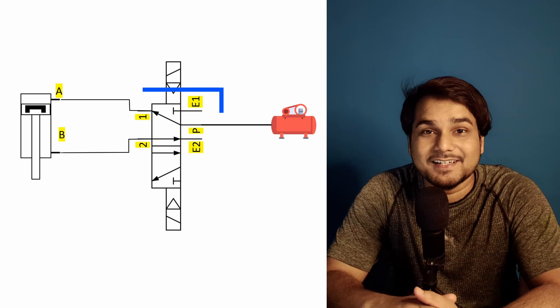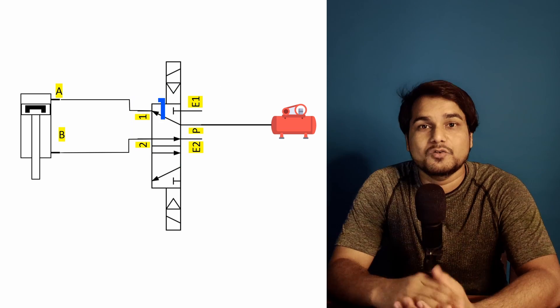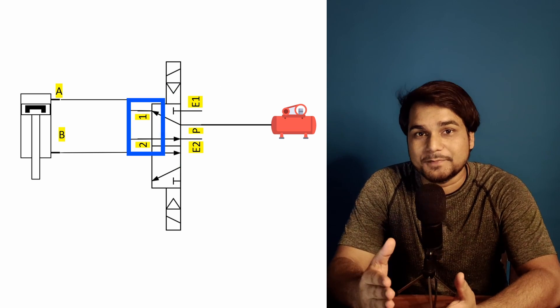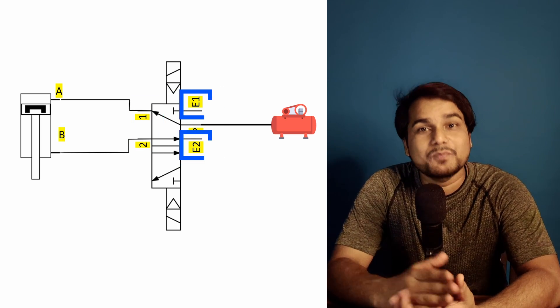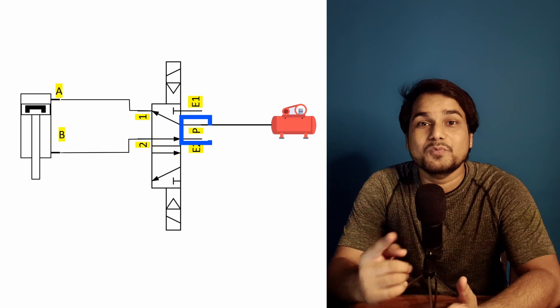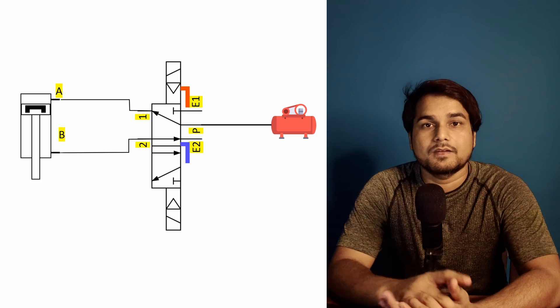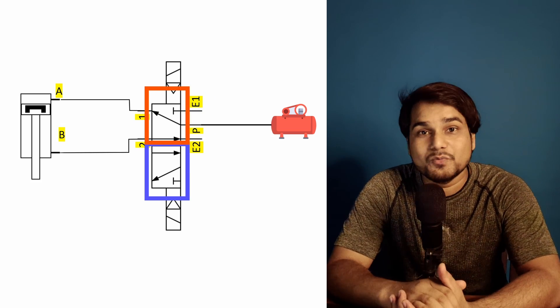So what is a 5/2 directional control valve? We can say a 5/2 directional control valve has 5 ports: 2 ports for connecting the actuator, 2 ports for releasing air (exhaust), and 1 port for supplying compressed air. A 5/2 valve also has two position states.